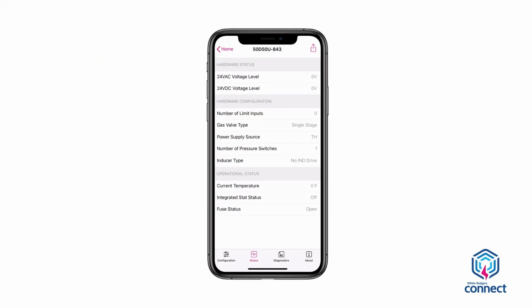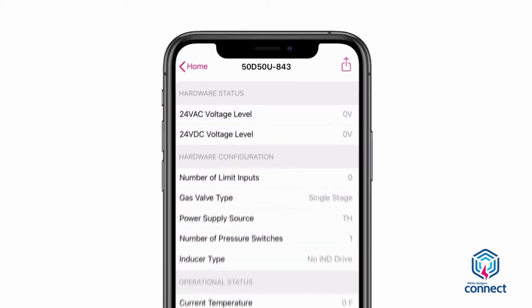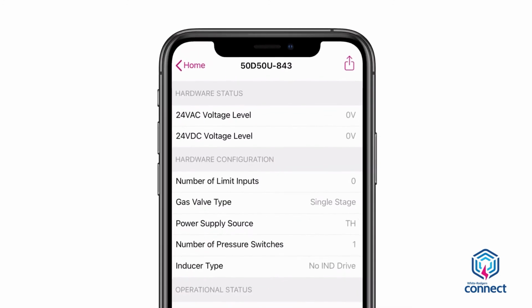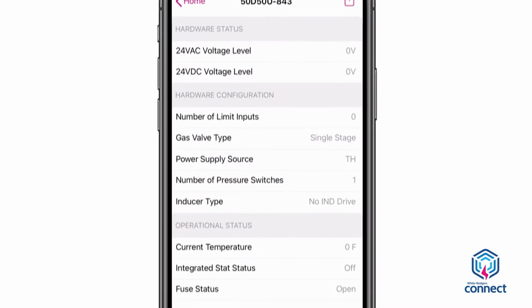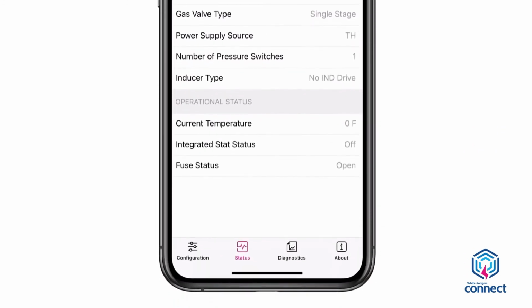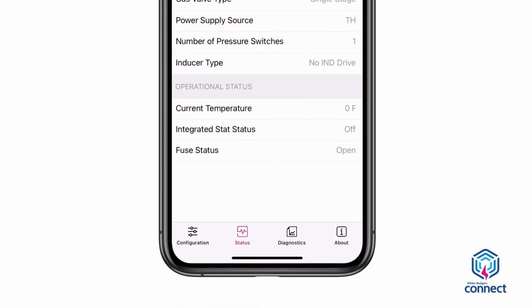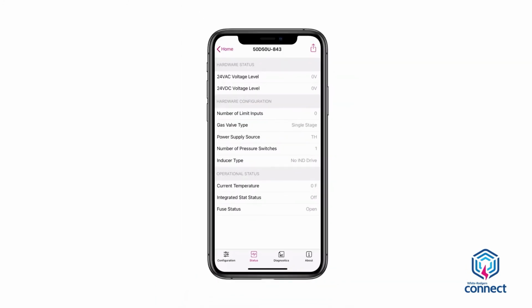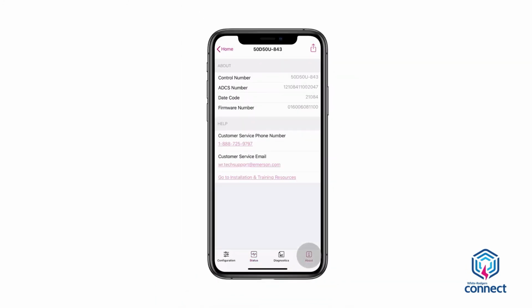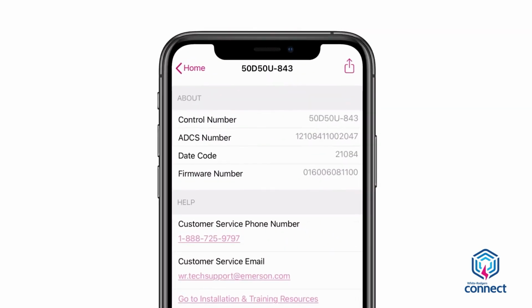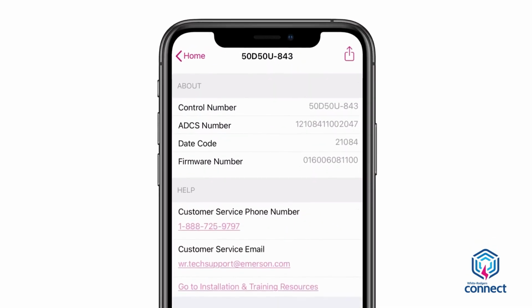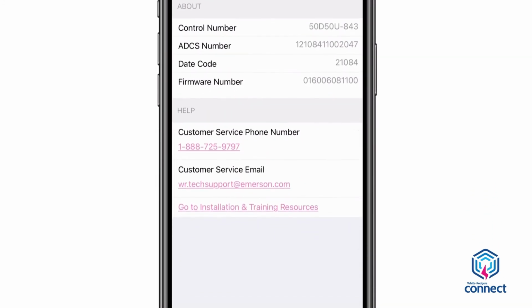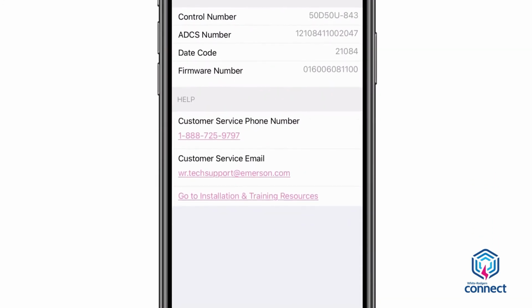Additional White-Rodgers Connect app features include System Status and information about the module. The Status tab shows the 24 volts DC and the 24 volts AC voltage level, the fuse status, and other status data applicable to the module. If at any time there are issues that require external support, White-Rodgers Connect comes equipped with an About tab that shows product information, the White-Rodgers customer service contact number, and helpful quick links to installation resources and information.